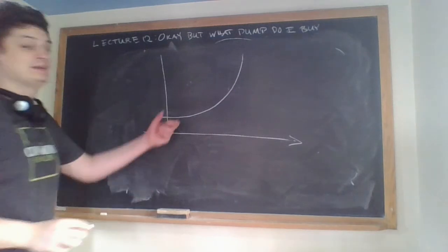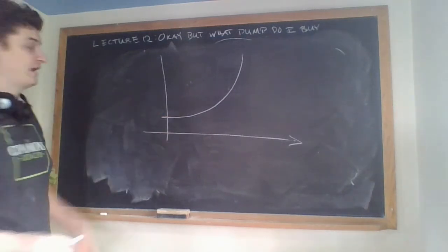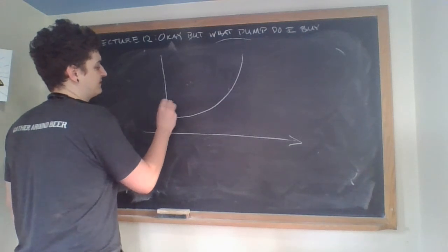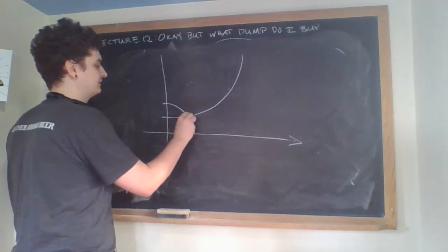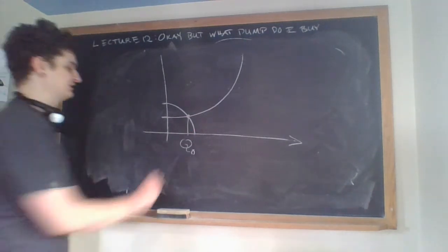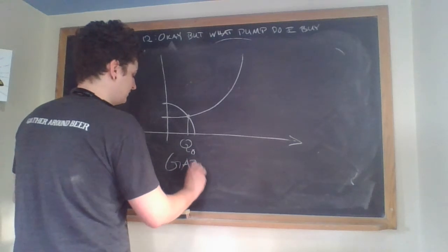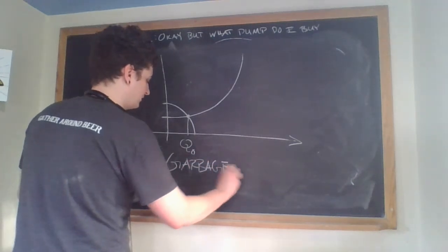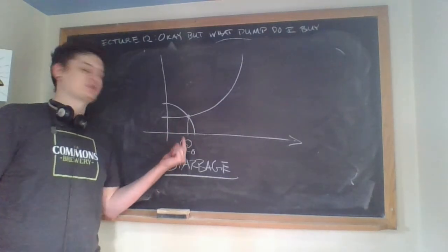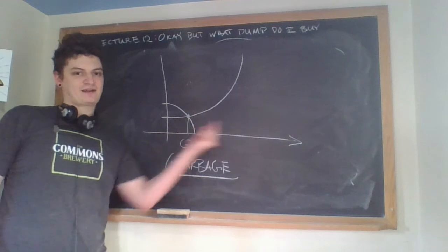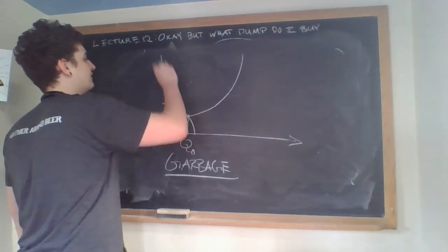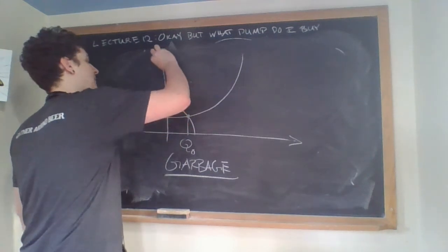Say I have a pretty steep system curve, okay? Right, steep system curve like that, and pumps I buy look like this. Here's my operating point there. So this is garbage. It's garbage because it's usually too low, right? I mean, your intersection point is just horrible, right? But you want to get this further out to a requirement, right? Well, series can help, right? Let's say I put 3 of them in series and I can really bump this up.